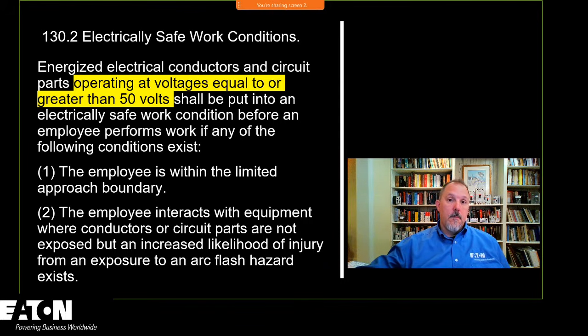And this is a very interesting concept from both the shock perspective and the arc flash perspective, because in 2015, we raised the low threshold from 50 to 100 based upon some data that we were provided with. And in 2018, we went back down to 50. But the key here is that OSHA is at 50. So if you're at 52, 54, or 58, you're over 50, so all of the rules would apply.